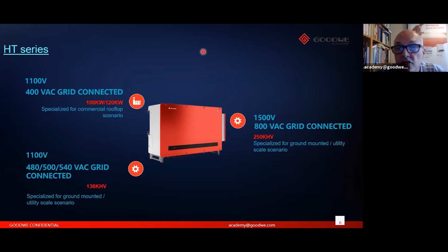On the right here, we have our 1500 volt DC connected inverter. Now these are connected to the grid at 800 volts, so you connect straight to a transformer with that AC voltage, and this is going to be very good for the power stations and the ground mount utility scenario. So that's our largest solution there, which is coming. Okay.